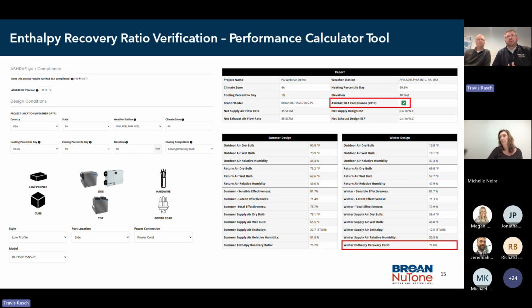I'll add that particularly in Climate Zone 5, due to colder weather, if you're going down the total performance path or energy modeling route, you'll likely find with dwelling unit ventilation needs that using an ERV gets you there. If you're introducing outdoor air with an ERV, you're recovering energy removed from the dwelling, so in your performance or energy modeling it's often advantageous to use that recovered energy to provide outdoor air that's tempered and filtered.